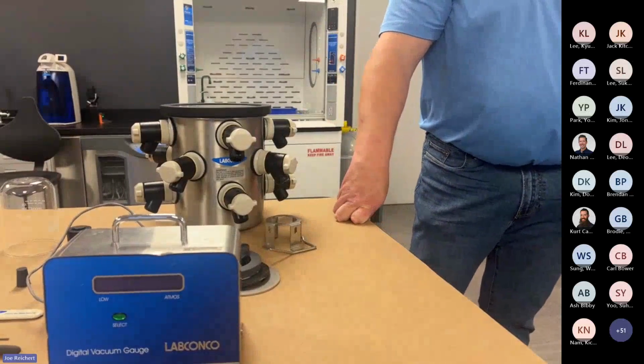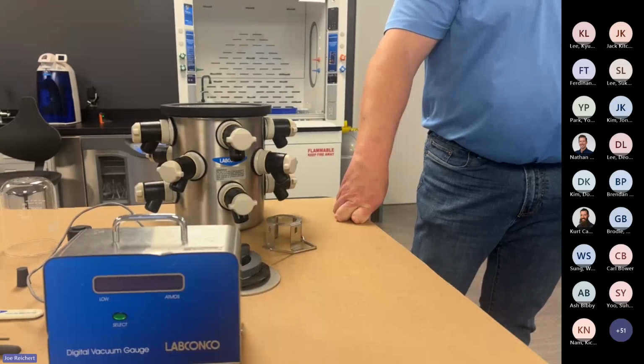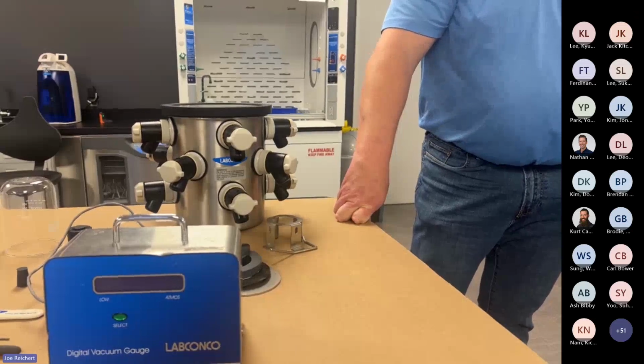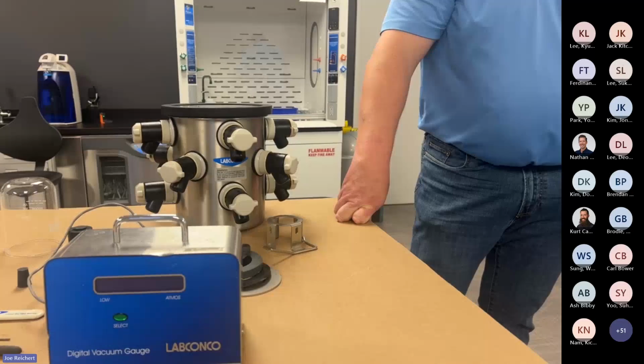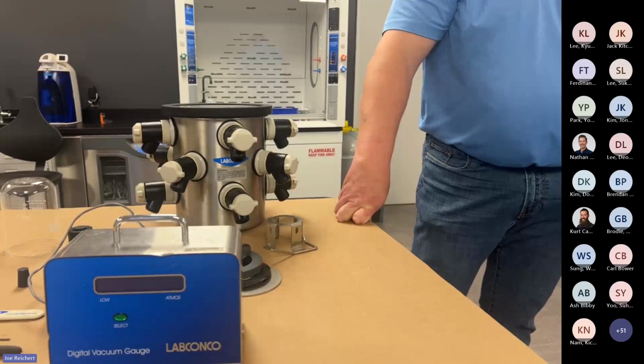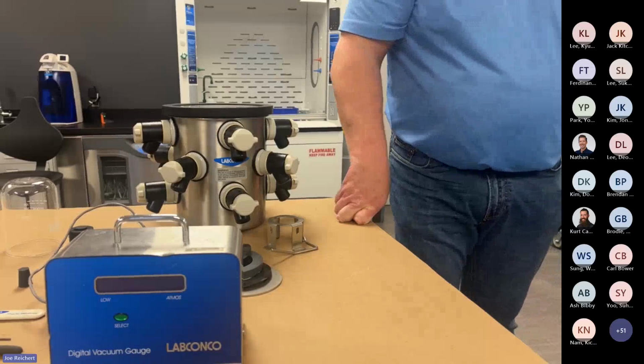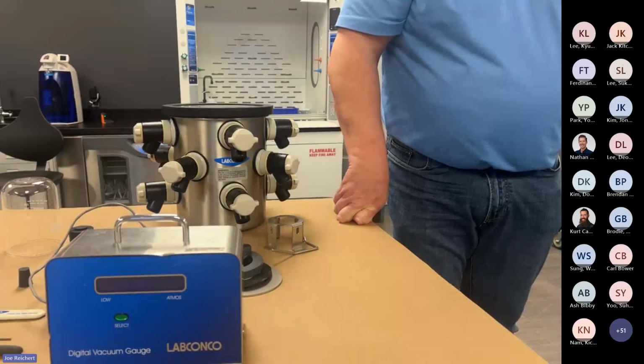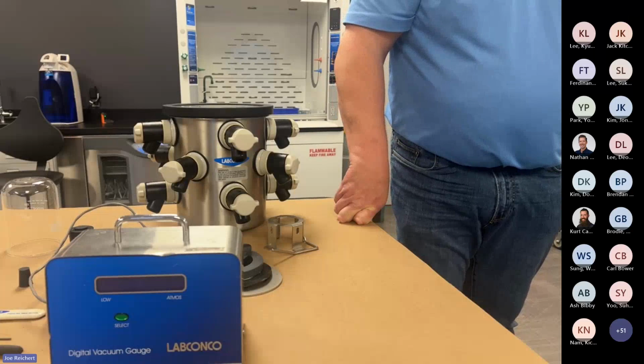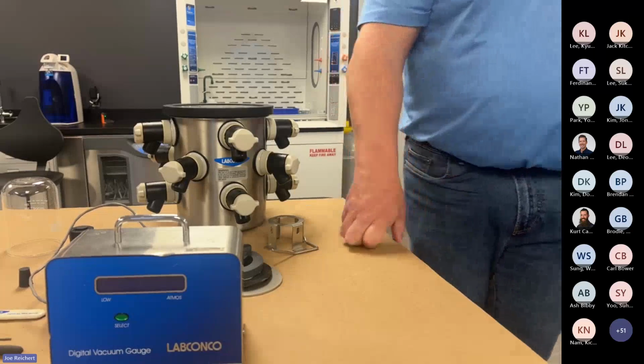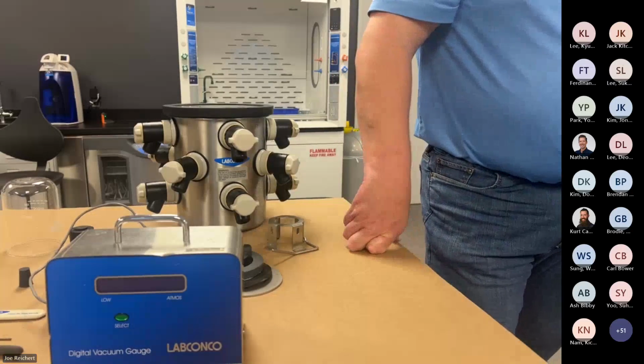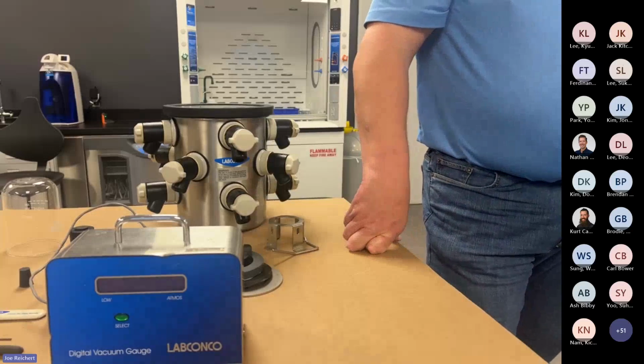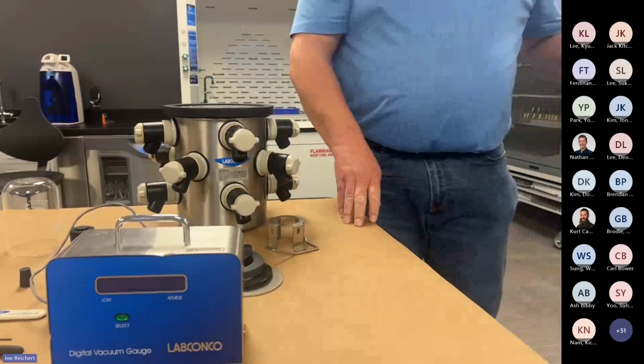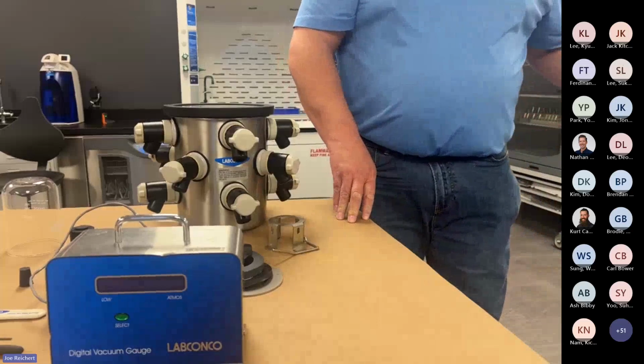But first, scroll pumps are our newest pump that we carry, and there is some setup to a pump when you have them new out of the box. So they have to be put into an auto mode. If you've ever installed one and noticed that as soon as you turn power on the freeze dryer to try to turn on the vacuum pump, it won't turn on. All you're getting is a light on the interface of the pump, and then it doesn't turn on.